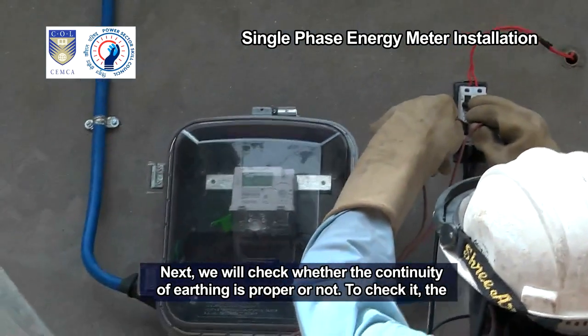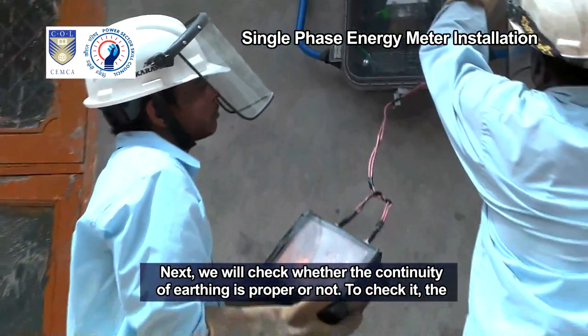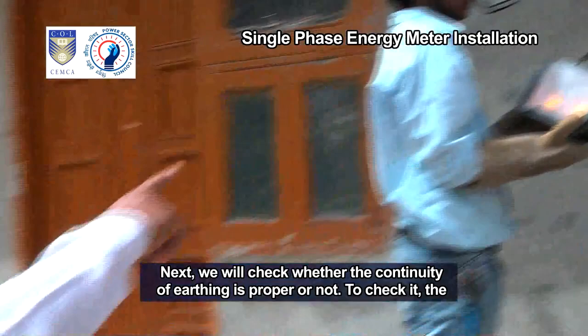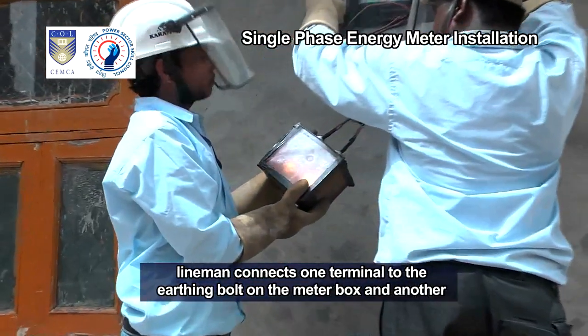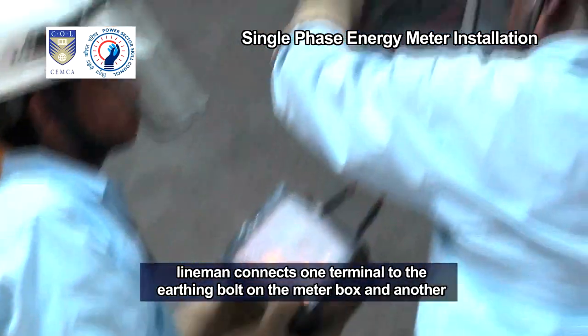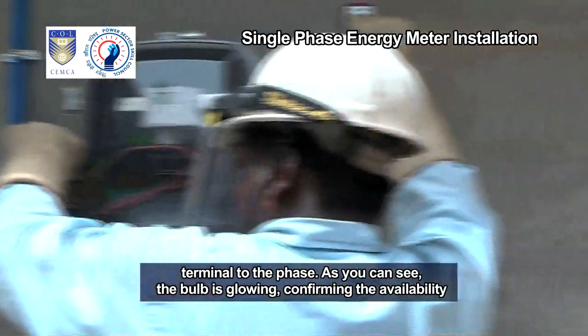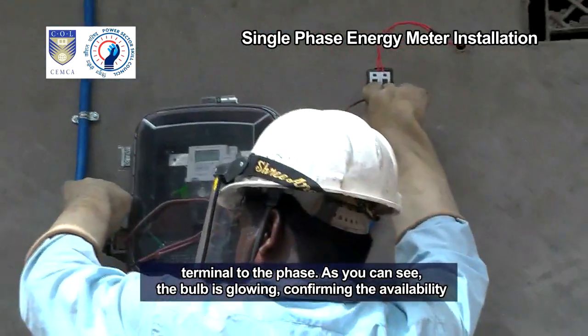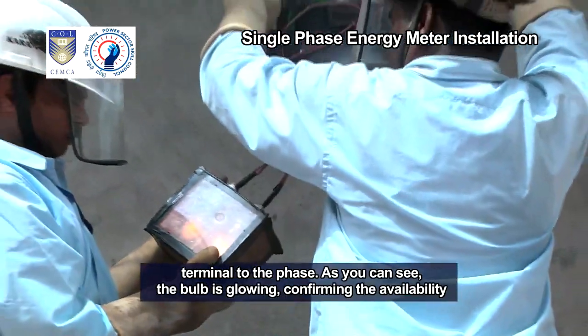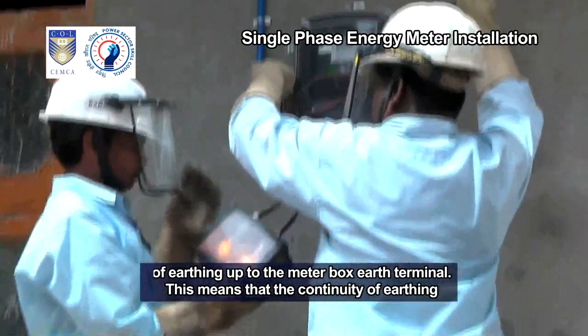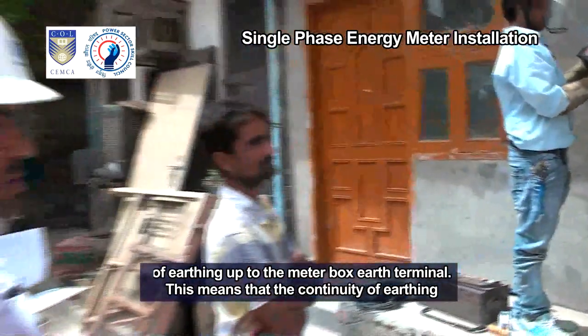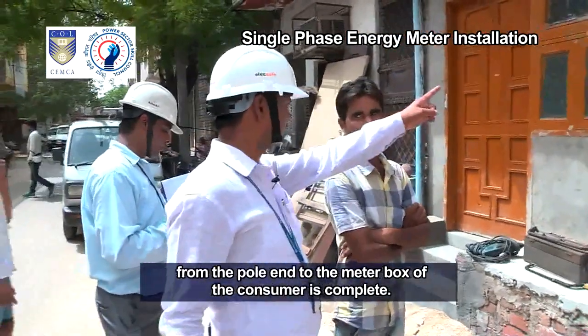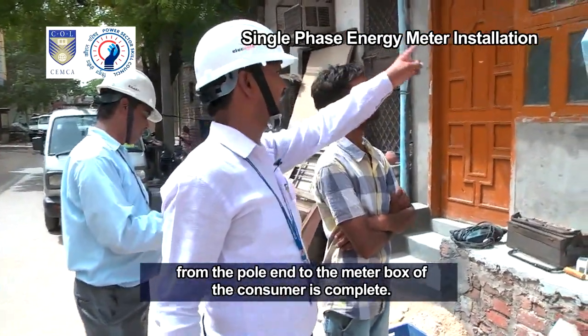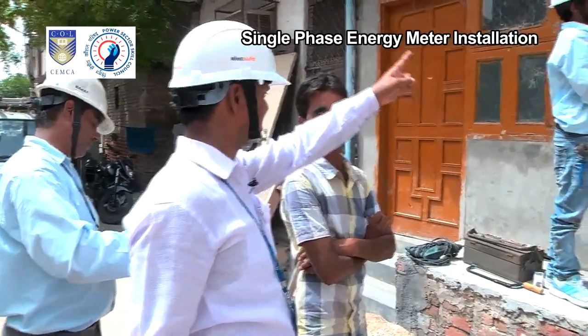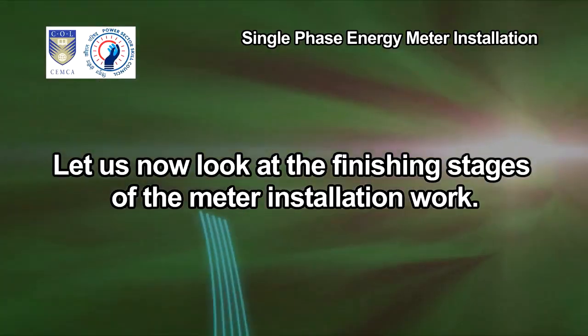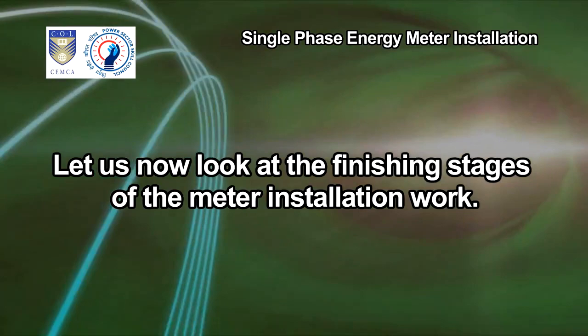Next, we will check whether the continuity of earthing is proper or not. To check it, the lineman connects one terminal to the earthing bolt on the meter box and another terminal to the phase. As you can see, the bulb is glowing, confirming the availability of earthing up to the meter box earth terminal. This means that the continuity of earthing from the pole end to the meter box of the consumer is complete. Let us now look at the finishing stages of the meter installation work.